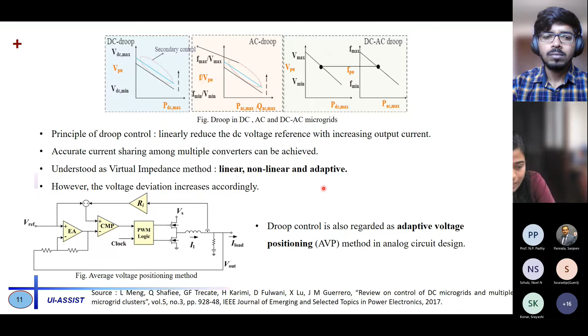Now we move towards the control layer modeling. The reason for showing this is that this is the primary layer control, and this is the secondary level control. The secondary level control consists of a voltage observer and a current observer for our test system. Basically, Sauradeep was trying to attain consensus in the state of charge of the batteries. But to fulfill our objectives, we needed the current in per unit to achieve consensus, and also maintain the average voltages throughout the DC microgrid to be the same.